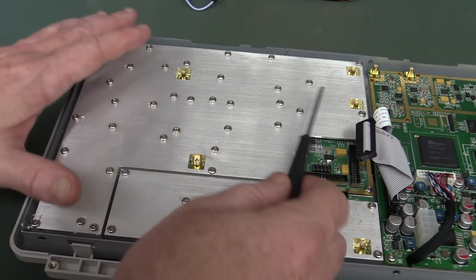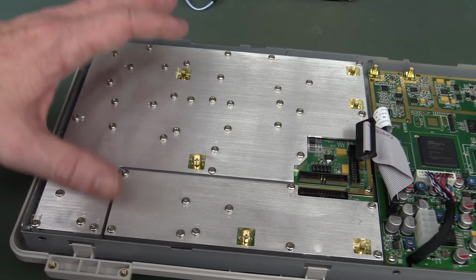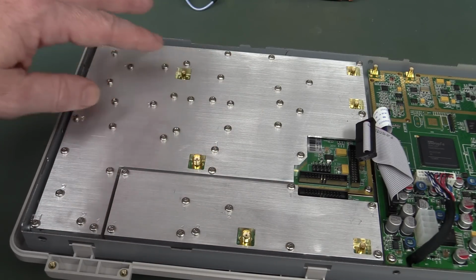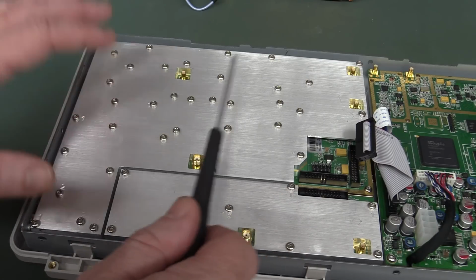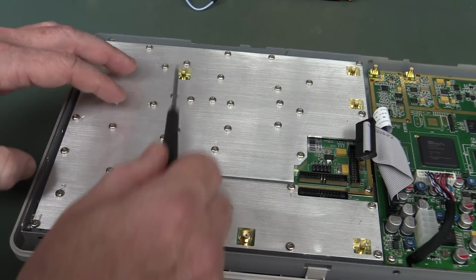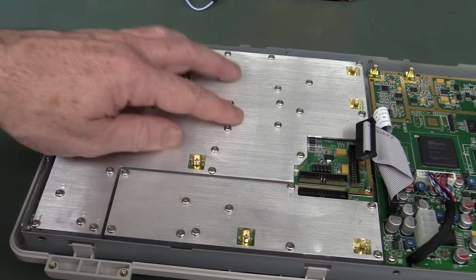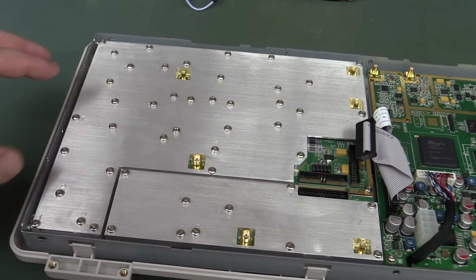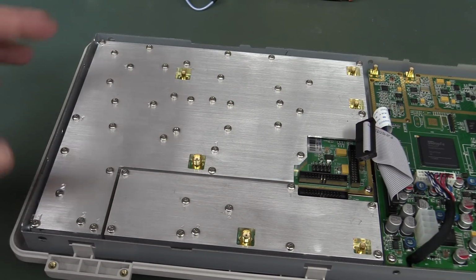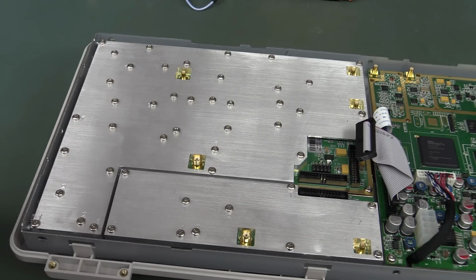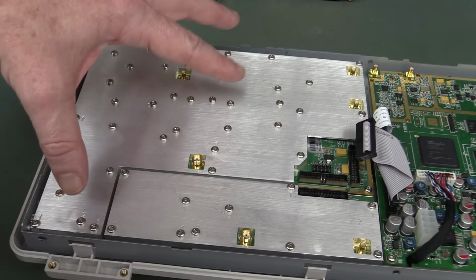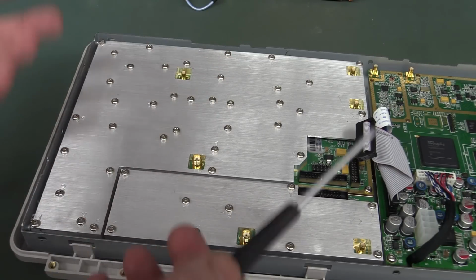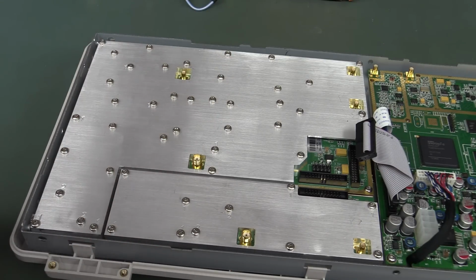And if you take out all the screws on the real bleeding edge high performance ones, and you disturb the gasket underneath, the pressure of the gasket separating all the sections, then you might have to get the thing recalibration checked. Just to make sure, because with the real bleeding edge RF stuff, it really matters. This is only a 3.2 gig one, so it's baby stuff in terms of RF. Real RF greybeards will probably go, ah, it's practically DC.